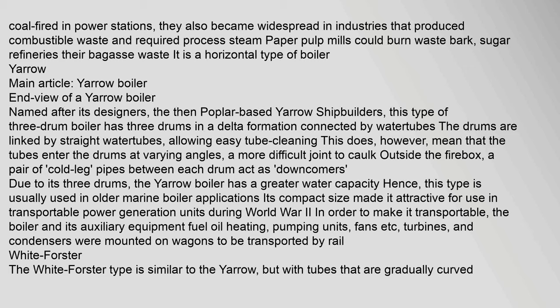The Yarrow boiler is named after its designers, the Yarrow shipbuilders. This type of three-drum boiler has three drums in a delta formation connected by water tubes. The drums are linked by straight water tubes, allowing easy tube cleaning, though the tubes enter the drums at varying angles — a more difficult joint to caulk. A pair of cold-legged pipes between each drum act as downcomers. Due to its three drums, the Yarrow boiler has a greater water capacity and is usually used in older marine boiler applications. Its compact size made it attractive for use in transportable power generation units during World War II.